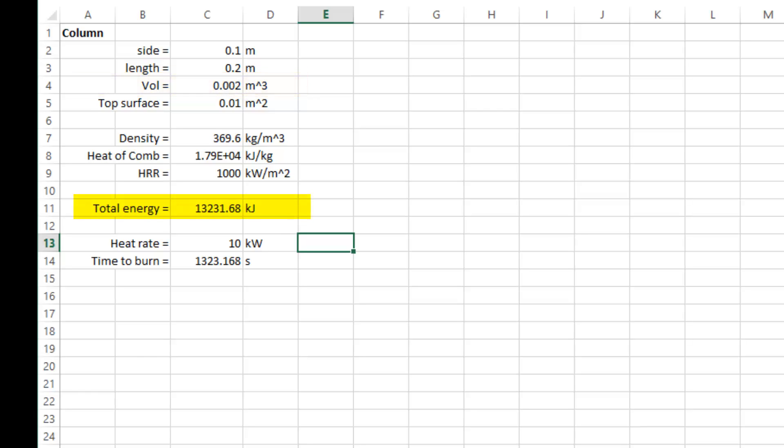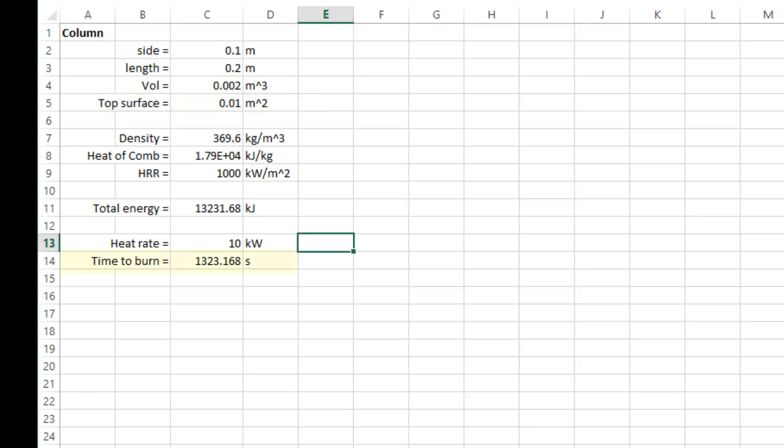So the total heat release will be 13,231 kilojoules. If we burn at a rate of 1000 kilowatts per meter squared on the top surface that has an area of 0.01 meter squared, the total time to burn away will be 1323 seconds.